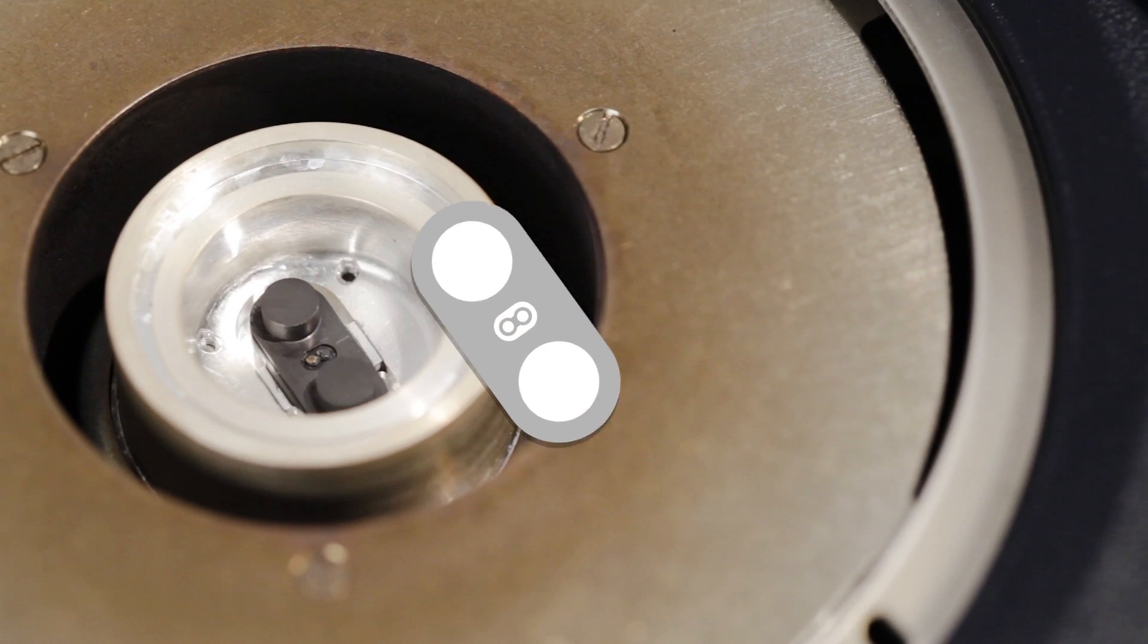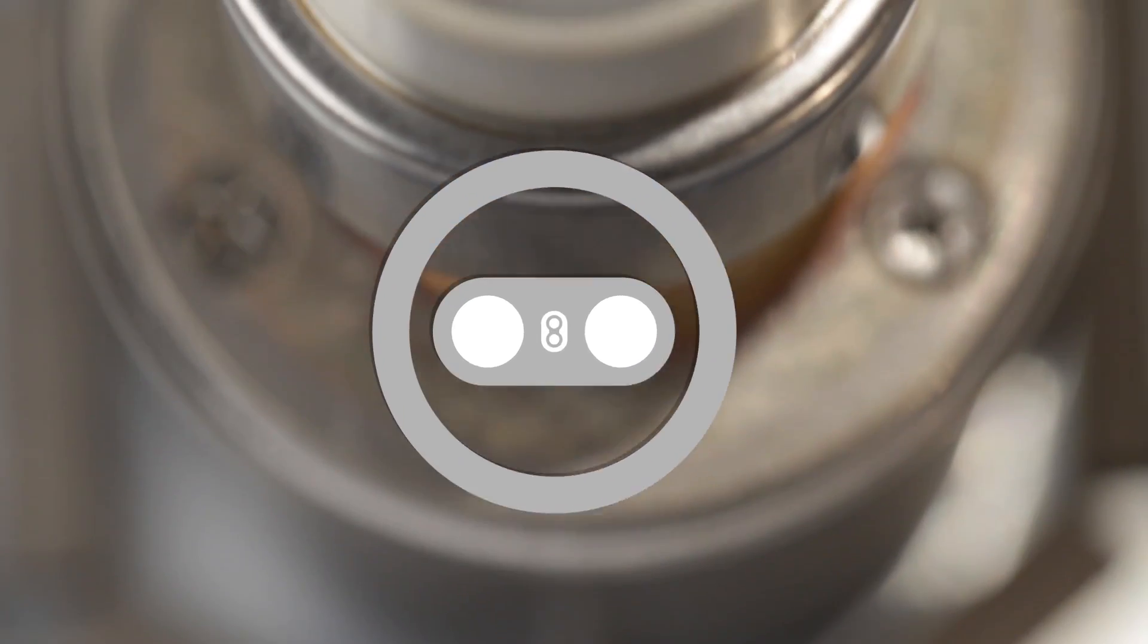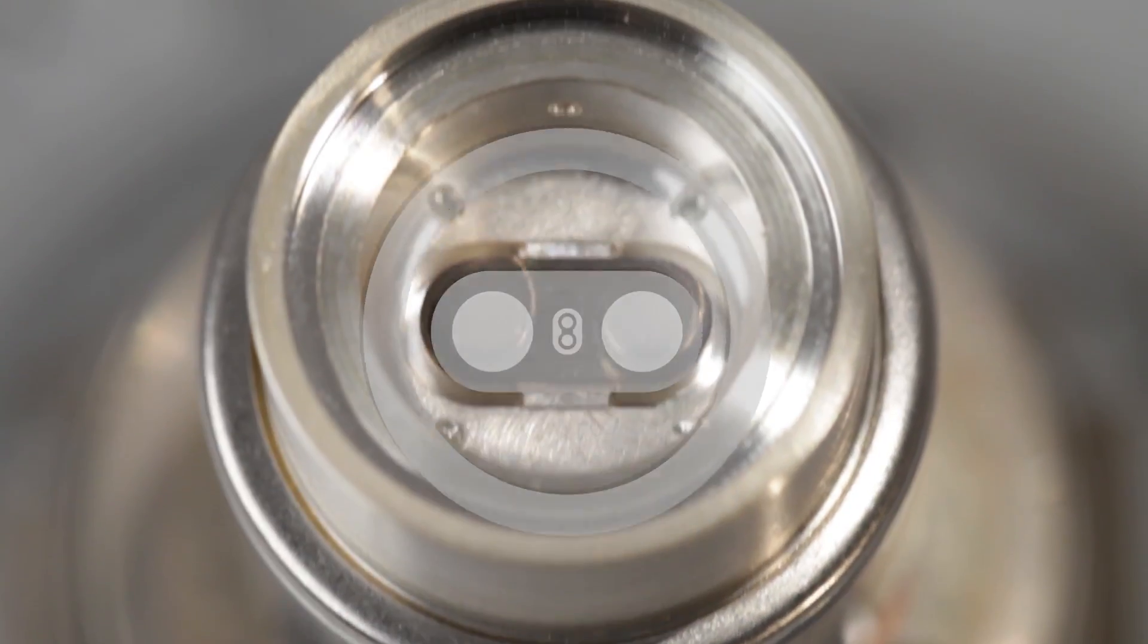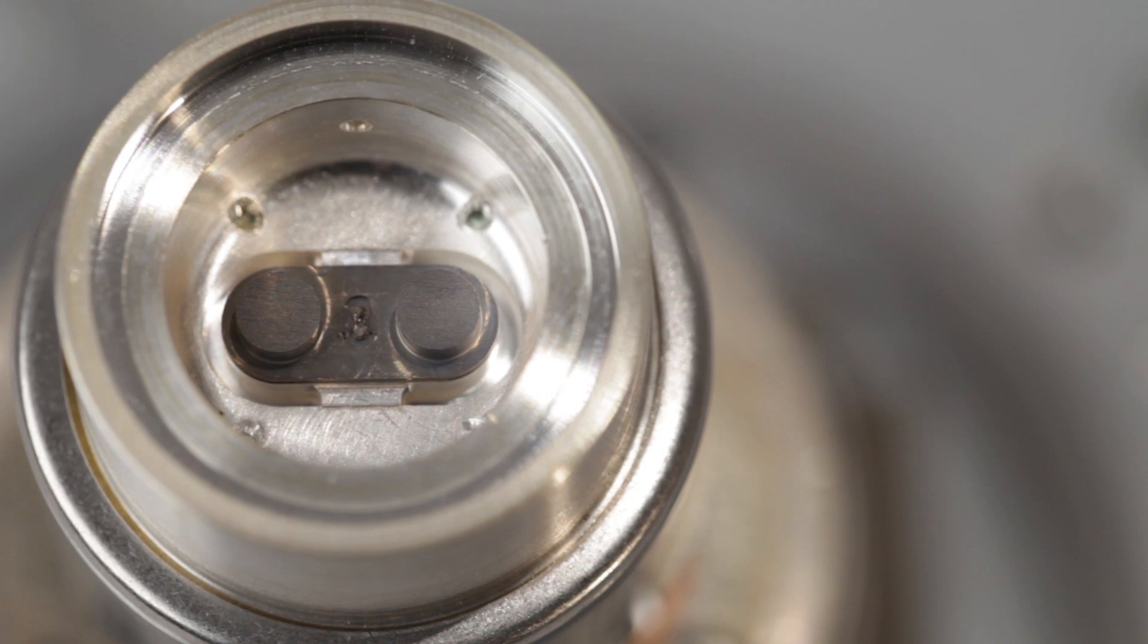At the core of every Discovery DSC is the new TA Fusion Cell and patented T0 technology. Unlike competitive designs, the Discovery DSC delivers high performance with a single sensor, eliminating the need to exchange sensors to optimize sensitivity or resolution.